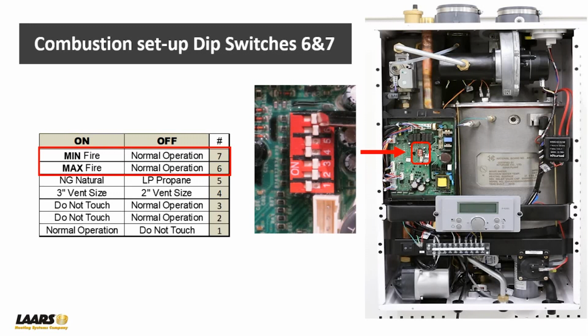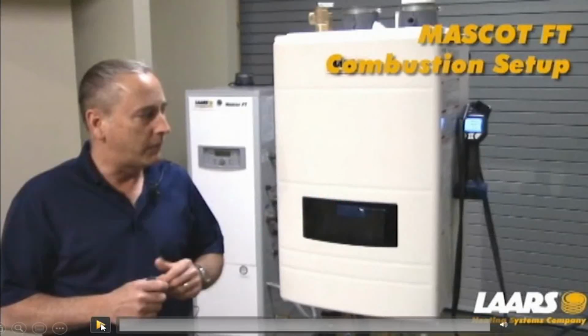And then go to low fire. Adjustments are only made in low fire here. So I do show you an example of that. So next would be throw dip switch 6 back to the normal position or the right-hand position. Dip switch 7 to the on position. You'll see your flame pattern in your sight window modulate right down. With your analyzer, check low fire as well. So we'll go in and play the video for you now.